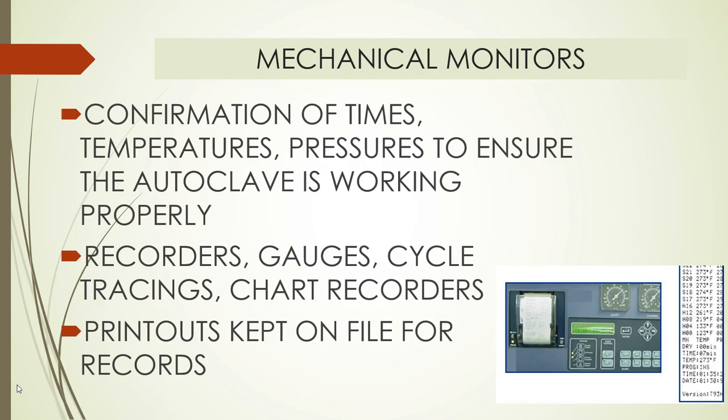It will confirm the appropriate temperature and confirm the appropriate pressures. And the autoclaves will have various recording devices and gauges and provide a printout. And again, you want to make sure that if this is the method by which you are monitoring your autoclave, that these are recorded, these are preserved, and that we are assuring that not only is this information available, but we are using that information to confirm that indeed the autoclave is working properly.